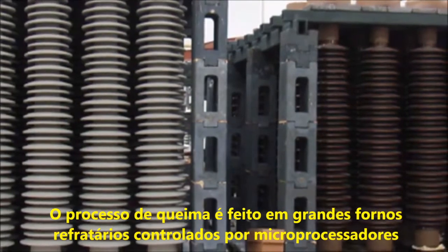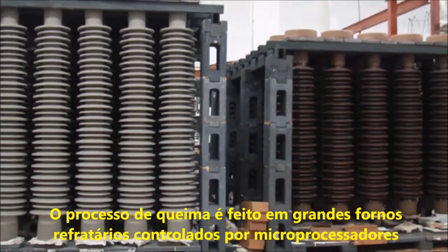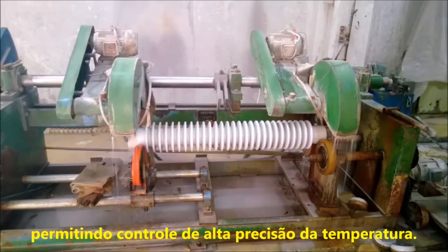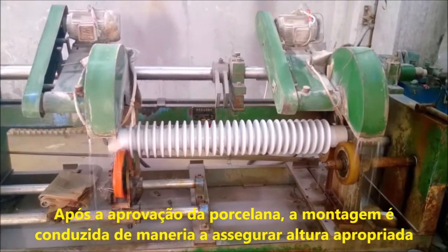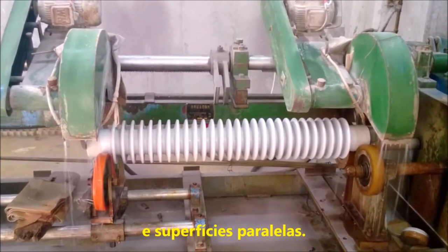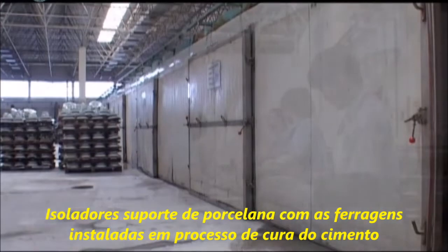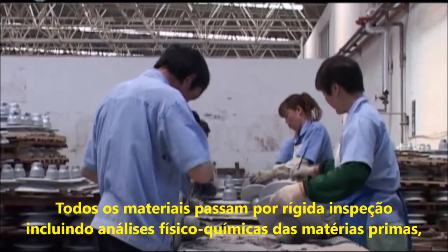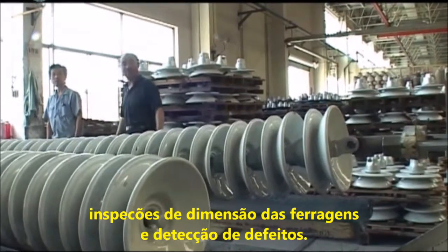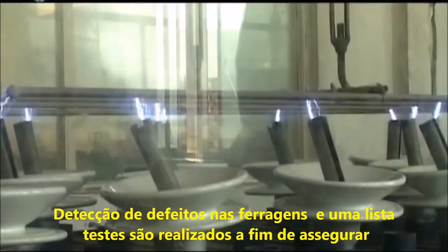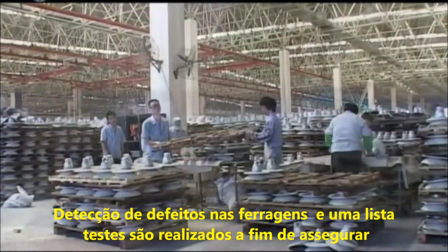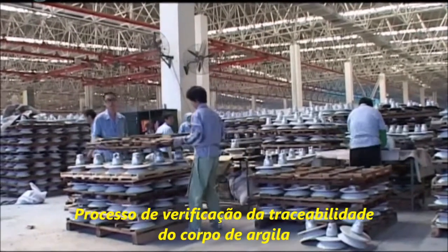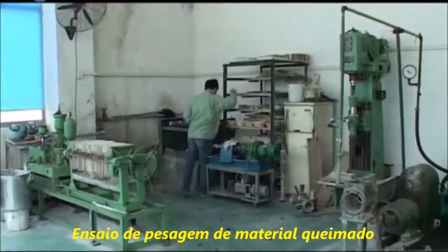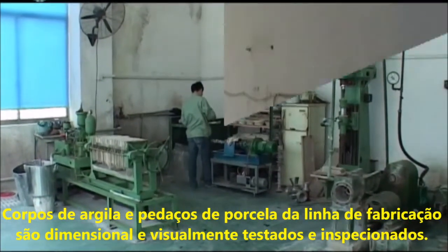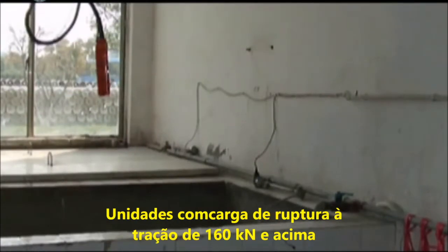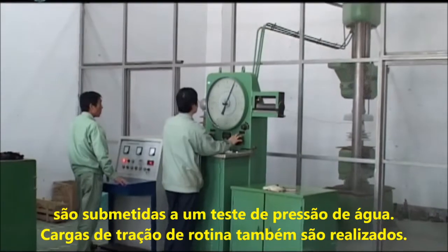The firing process is done in large shuttle kilns, all of which are controlled by microprocessors, allowing for precision temperature control. After the porcelain is qualified, assembly is conducted in a manner which assures proper height and parallel surfaces. Binding post-insulator porcelain. All materials receive strict inspection, including raw materials, physical and chemical analysis, metal fitting dimensional inspection and defect detection. Adhesive checks are done to assure proper compliance to specification. Process of mud index test. Firing scale test, blank test, and porcelain pieces are visually and dimensionally inspected. Units with ratings of 36,000 pounds and above undergo a water pressure test.